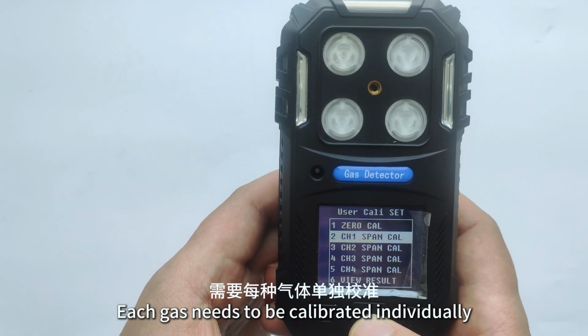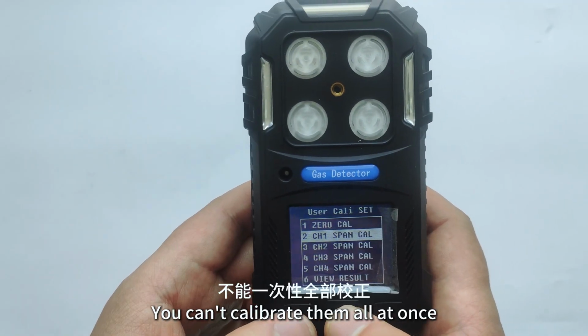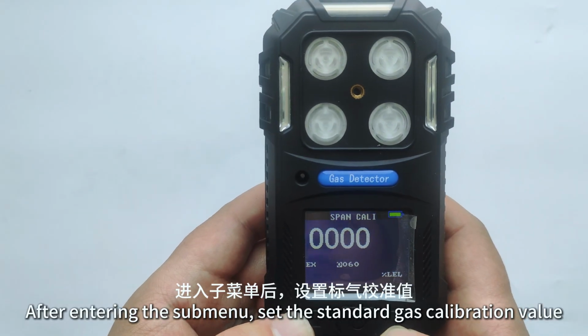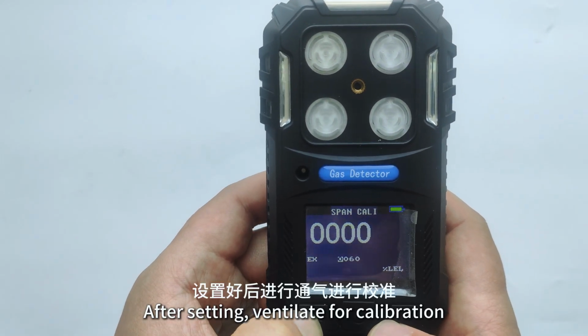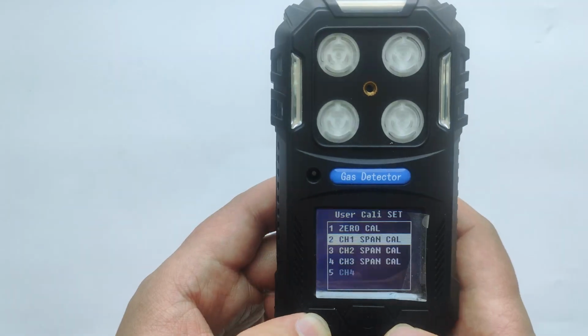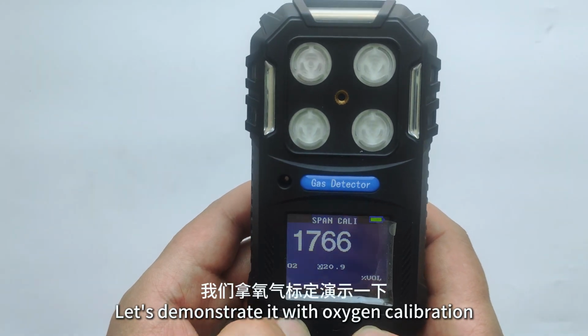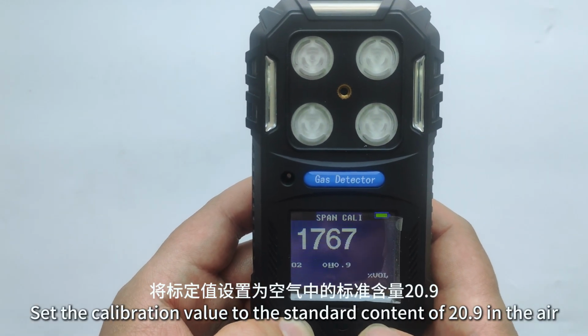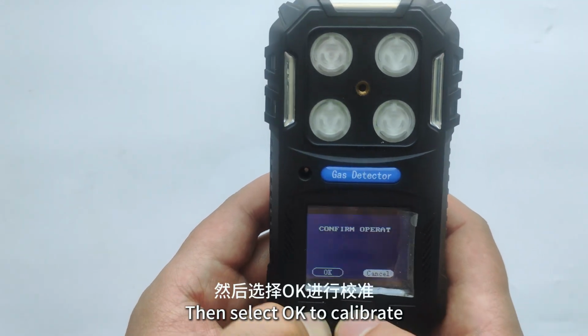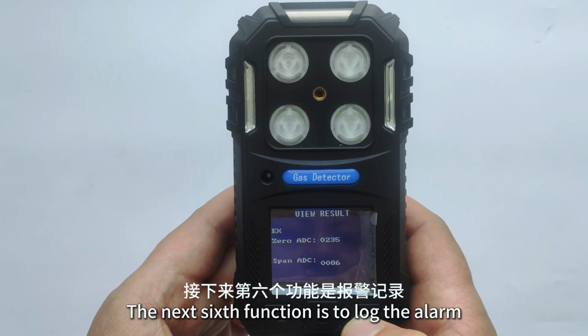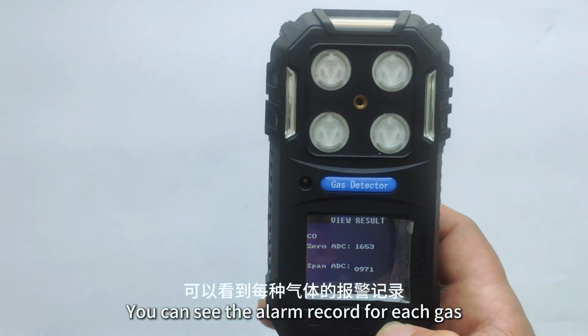Each gas needs to be calibrated individually. You can't calibrate them all at once. After entering the submenu, set the standard gas calibration value. After setting, ventilate for calibration. Let's demonstrate it with oxygen calibration. Set the calibration value to the standard content of 20.9 in the air. Then select OK to calibrate. The next 6th function is to log the alarm. You can see the alarm record for each gas.